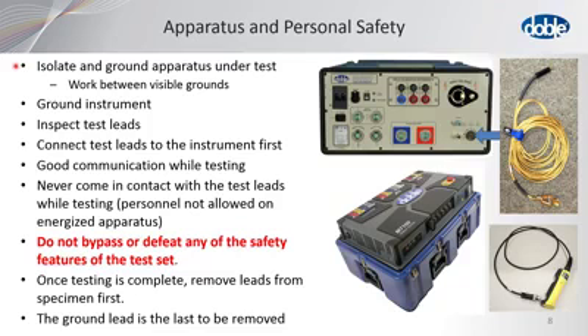Once the testing is complete, remove the leads from the specimen first. So if there's any situation where you don't need a lead, you should remove it from the top of the transformer, put it down on the ground, and then disconnect it from the test set. The ground lead should be the last one to be removed. I didn't point this out before, but this is a picture of the ground lead, and this is the connection for the ground in the M4100. And then along this is another receptacle for the ground lead for the M7100.